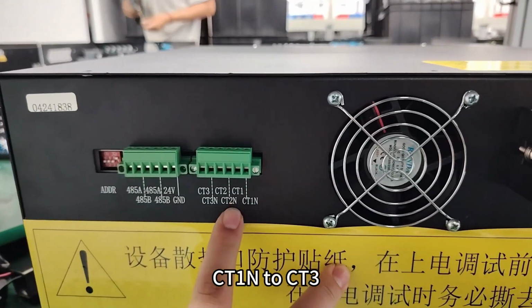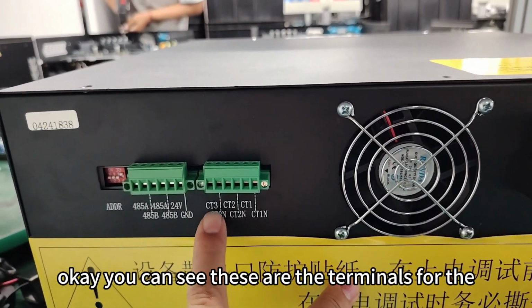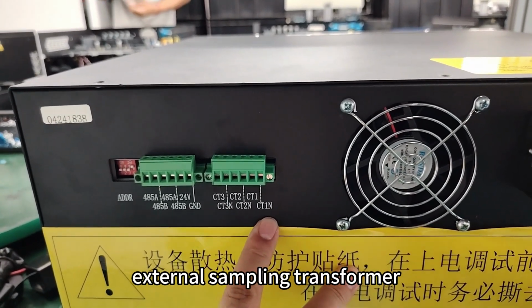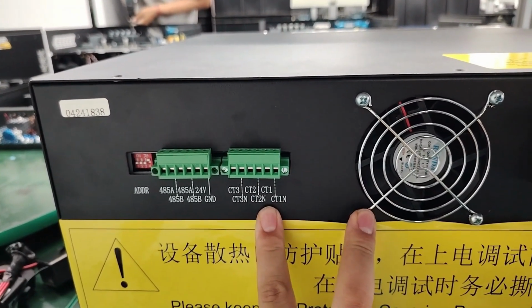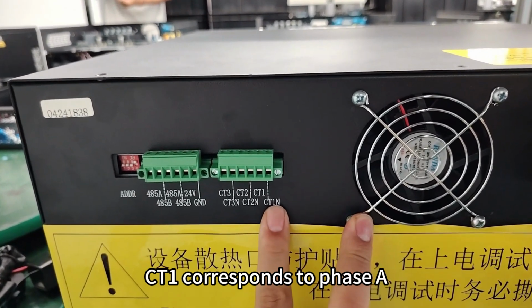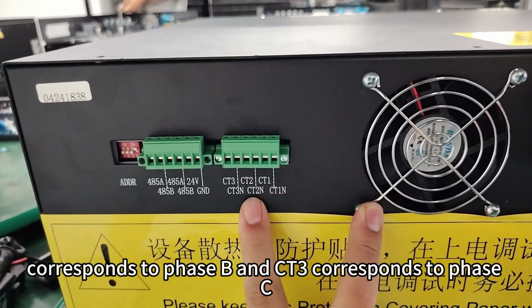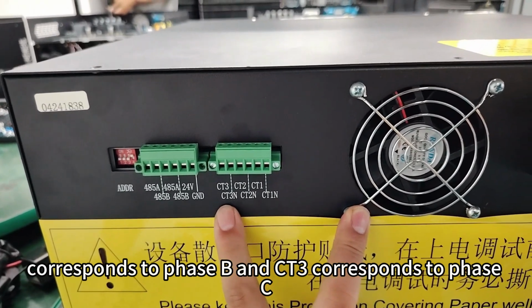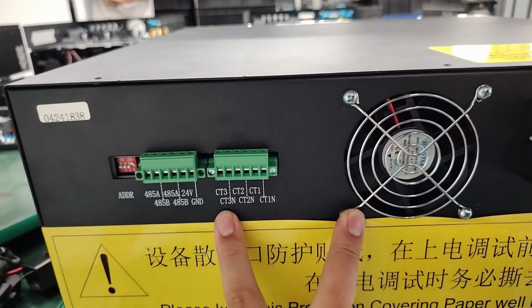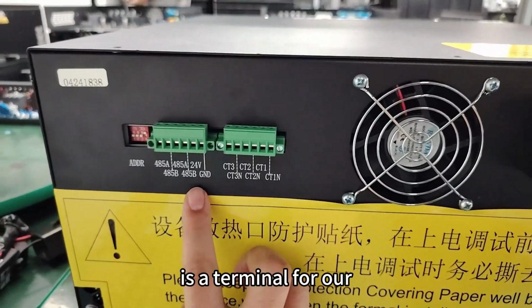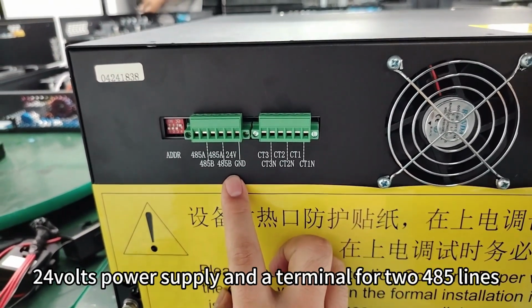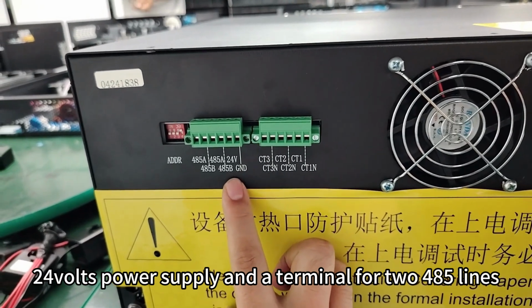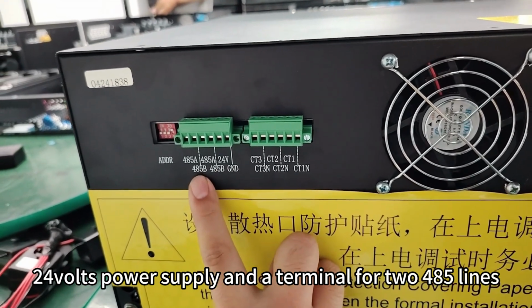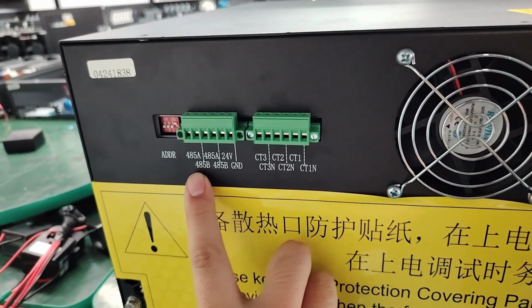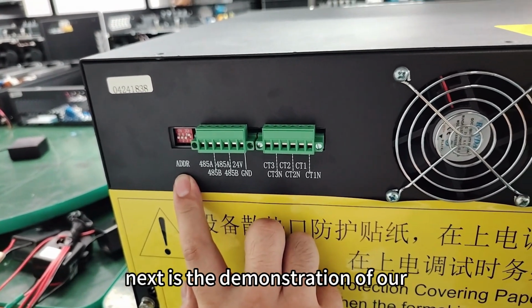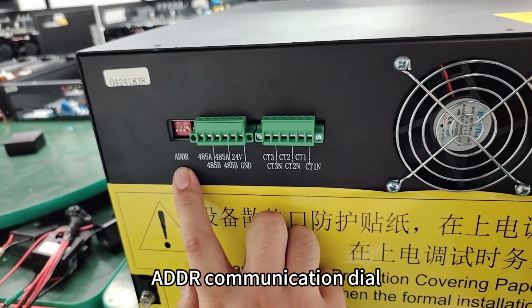Okay, let's see the left. CT1N to CT3. You can see these are the terminals for the external sampling transformer. CT1 corresponds to phase A, CT2 corresponds to phase B, and CT3 corresponds to phase C. Then to the left is the terminal for our 24 volts power supply and a terminal for two 485 lines.